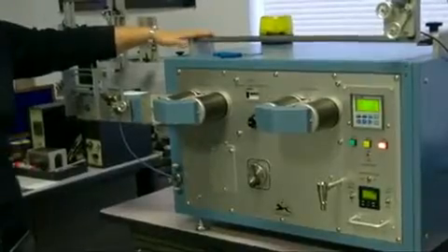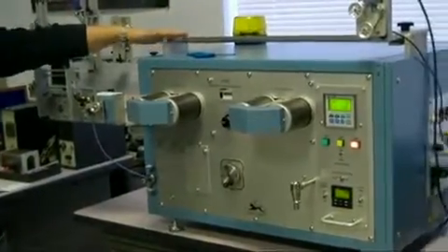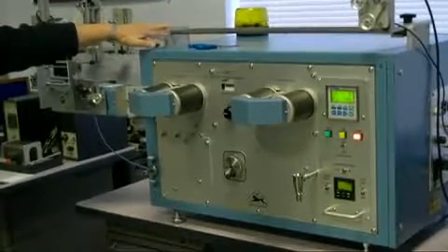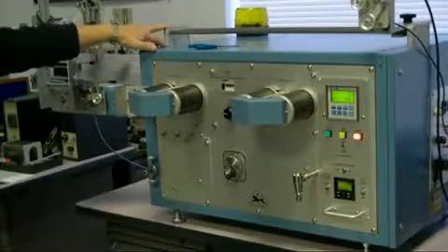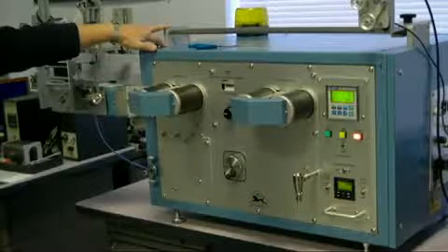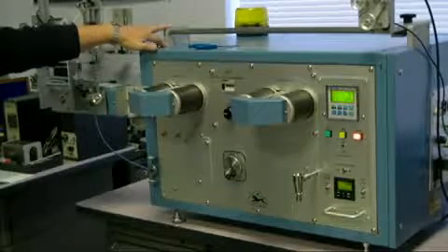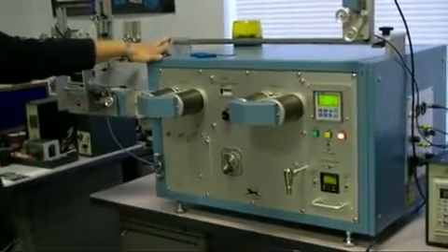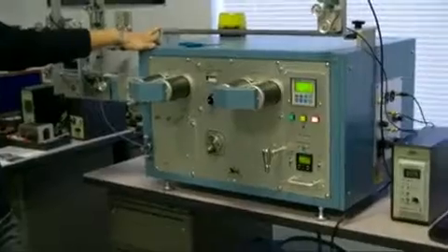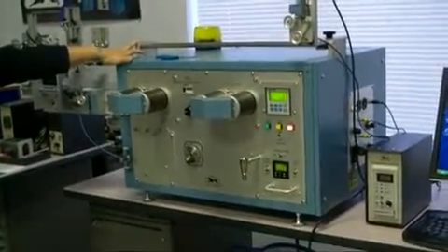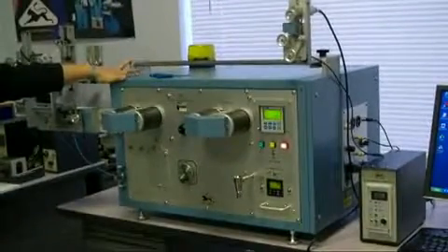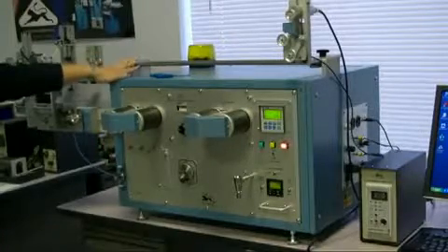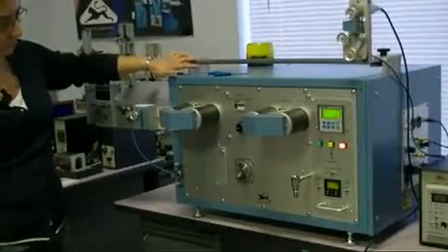The CTT comes in two different models, CTT Basic and CTT Extended Range. The difference is the capacity between the machine's ability to measure elongation and shrinkage. For example, the CTT Basic will measure elongation and shrinkage up to 25%, whereas the CTT Extended Range will measure elongation up to 200% and shrinkage up to 65%. As I said, this machine is CTT Extended Range.